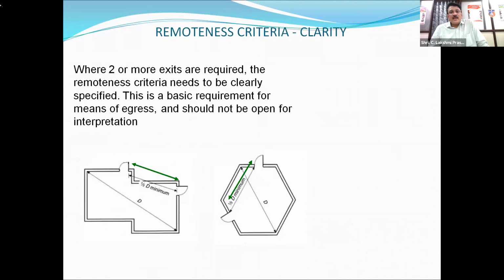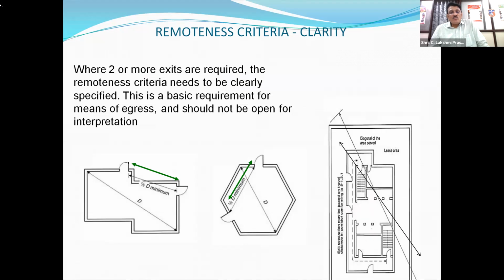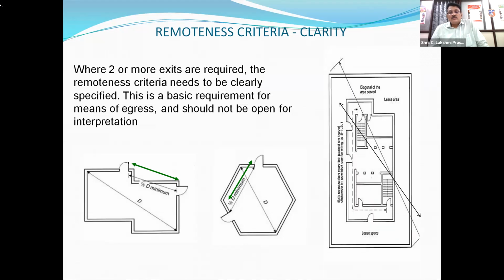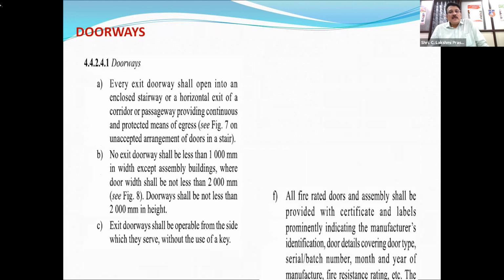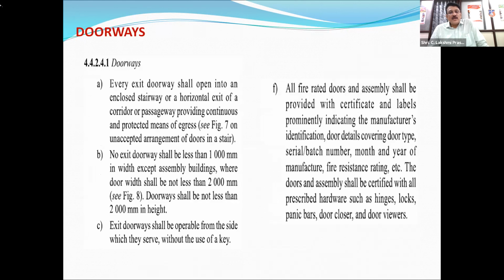So, remoteness criteria: I told you the staircases have to be staggered and they should be remote from one another. In other international codes, they have specified how far apart two staircases should be and how much they should be staggered. But in our code, it all depends on three factors: the travel distance, dead end corridor, and meeting the occupant load. Then doors also should be protected, and the minimum width of the doors is also given.